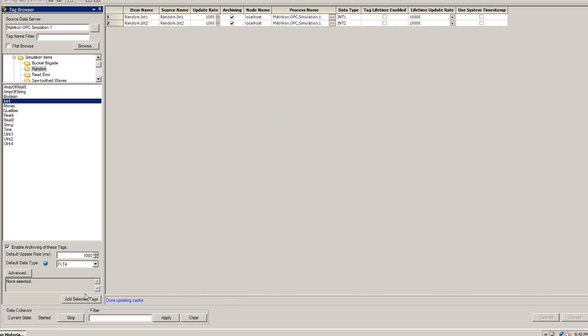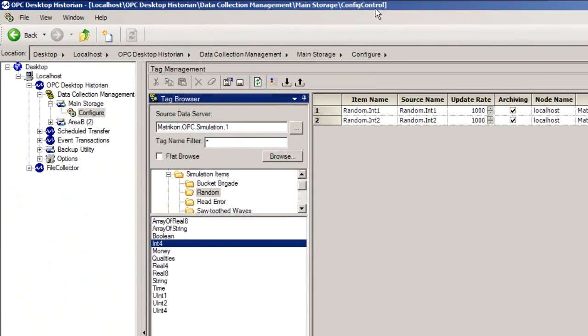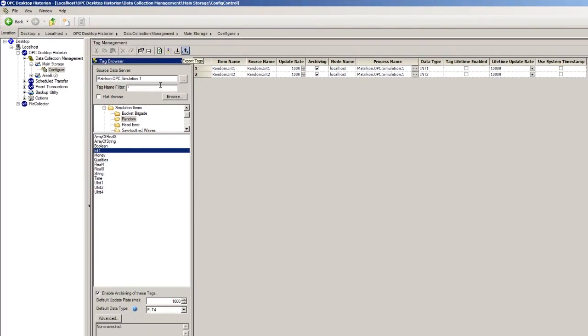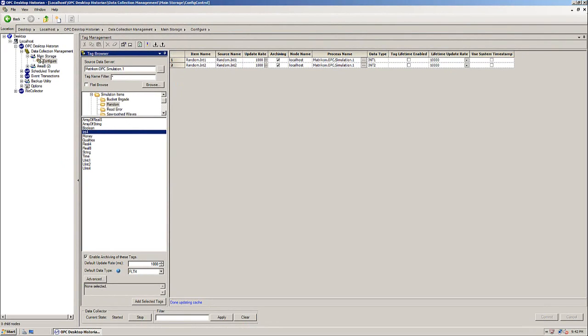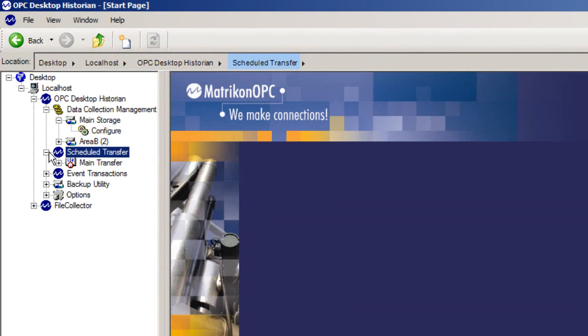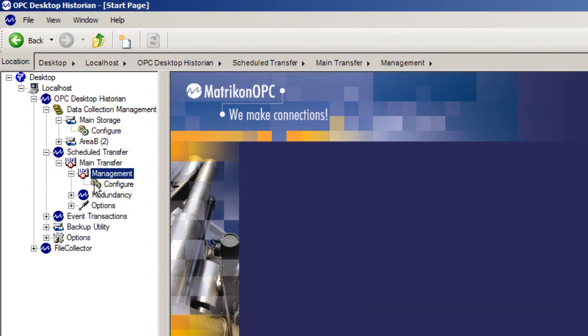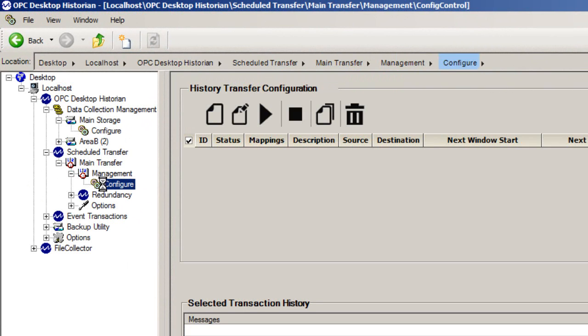The tags chosen are now archiving. For bulk imports to this configuration area, these new buttons allow for CSV import and export. While we have the GUI open, you can see how the HistoryLink product has been nicely integrated in here. This saves you time in not having to open a separate GUI. The Scheduled Transfer tab is where you can configure the data from Desktop Historian to be pushed to another OPC-HDA server. Note that this option will only be available if you choose Hub and Spoke when installing.